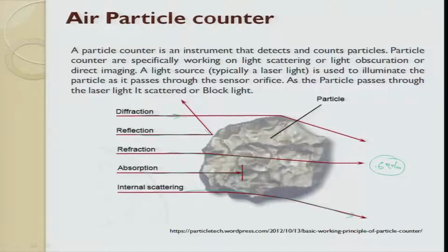So, if we are having a particle size of 1 micrometer, it is 65% of the actual size. So, it has to be calibrated accordingly, right.